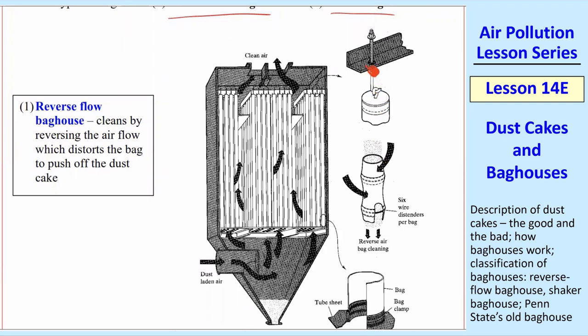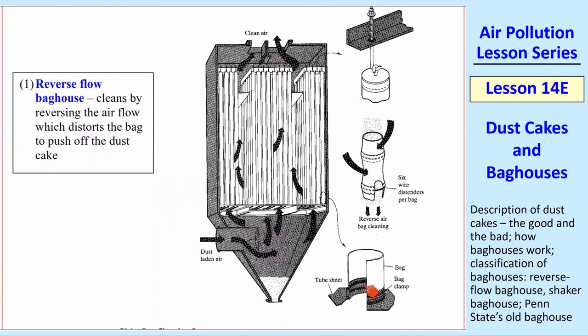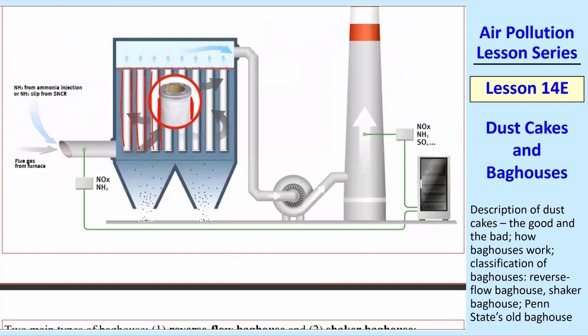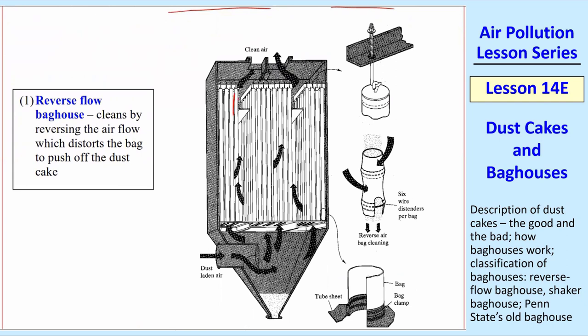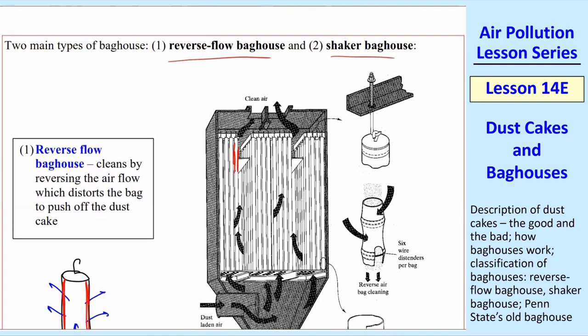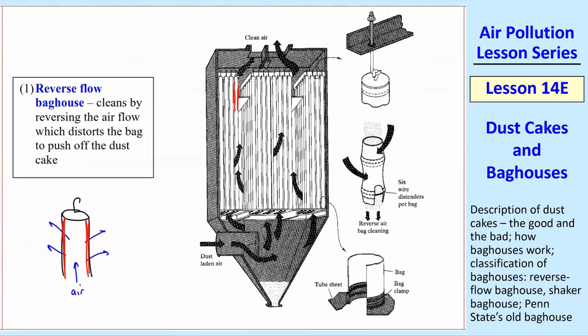A reverse flow bag house cleans by reversing the airflow, and that distorts the bag to push the dust cake off. In this schematic, these bags are hanging from the top. This is the kind where the air comes into the inside of the bag — the air comes in, goes through the inside of the bag, and then the clean air comes out and is collected at the top. So whereas in that case the dust cake builds up on the outside of the bag, in this case the dust cakes build up on the insides of the bags — very similar to the bag on your vacuum cleaner at home. Air comes into the middle of the bag and goes through it, so the dust cake buildup is on the inside of the bag. Those are just two different ways of creating a bag house: you can have dust collect on the outside or the inside of the bag.